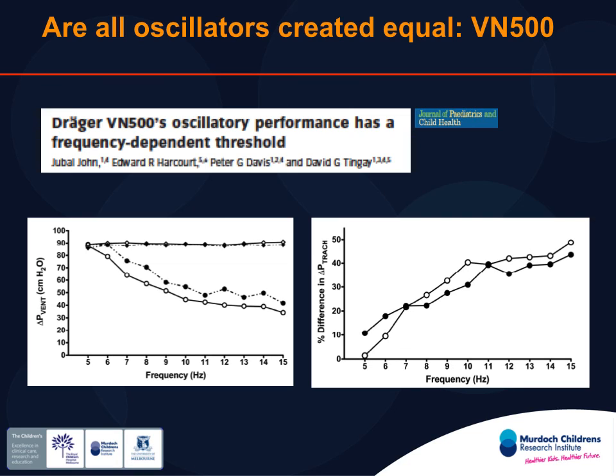And because we were interested in this change in delta P that was occurring with frequency, we found in the test lung that, unlike the Sensormedics, there was a relationship between frequency and the absolute maximum delta P you could generate. In this test, we set both devices to a delta P of 90 centimetres of water, because that's the maximum the VN said it could produce. I suggest that you're probably not going to use that delta P, but we did it because we didn't want the machine's performance to be limited by us. And the Sensormedics sets 90 and it just delivers 90.